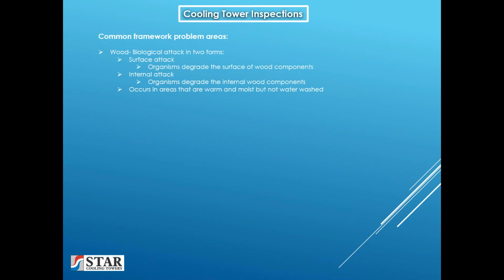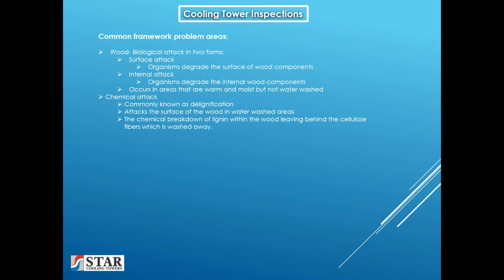And it occurs in the areas that are warm and moist, such as the plenum area, but not in the fill areas, the water washed areas. The microorganisms aren't able to grow. Chemical attack, commonly known as delignification, attacks the surface of the wood in water washed areas. The chemical breaks down the lignin within the wood, leaving behind the cellulose fibers, which are washed away. The danger of this type of attack is that it reduces the overall size of the timbers, sometimes as much as a half to 1 inch in an older tower. And this reduction in size is proportionate to the reduction in strength and can significantly reduce the structural integrity of a wood framework.